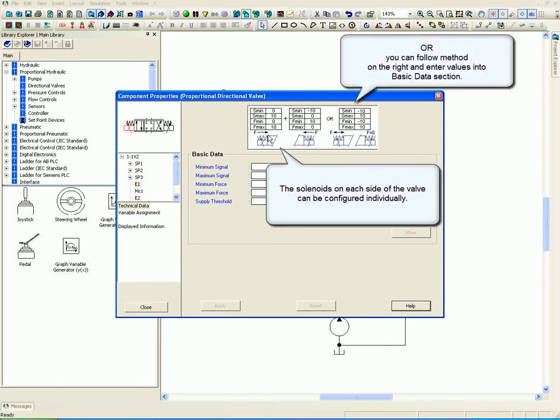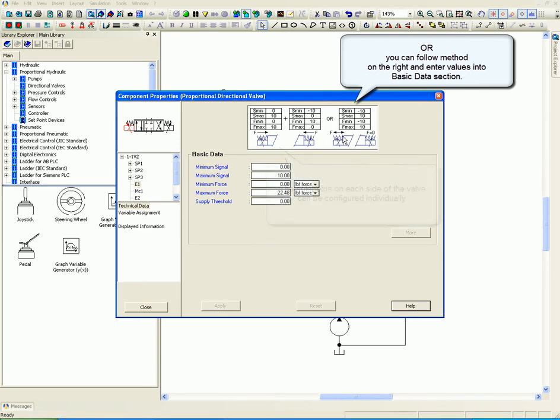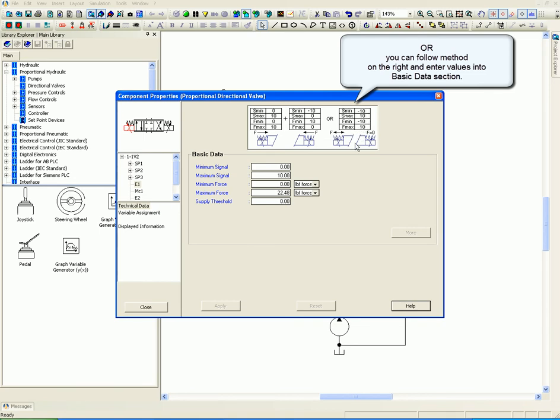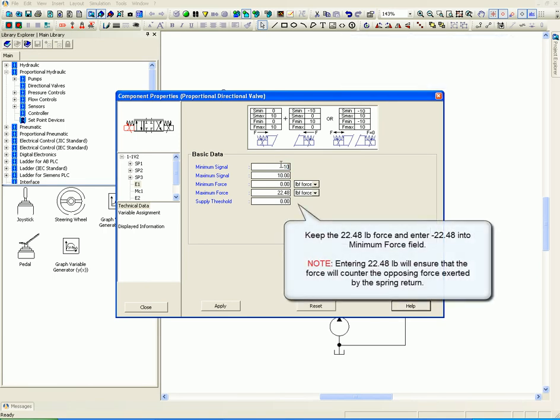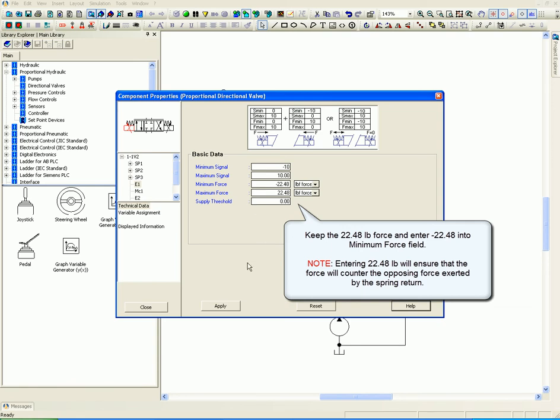Or, you can follow the method on the right and enter values into the basic data section. Keep the 22.48 pound force and enter negative 22.48 into the minimum force field. Entering 22.48 will ensure that the force will counter the opposing force exerted by the spring return.